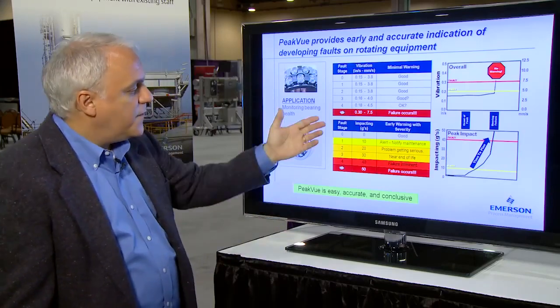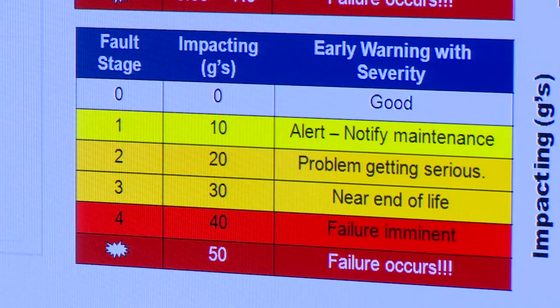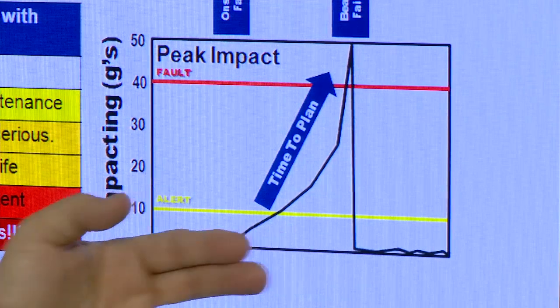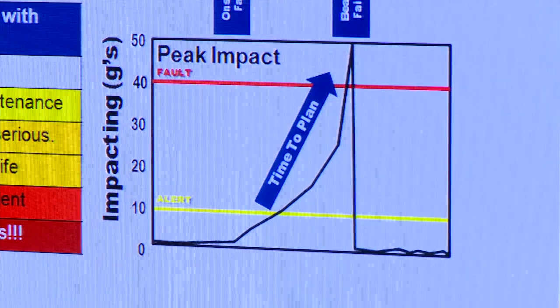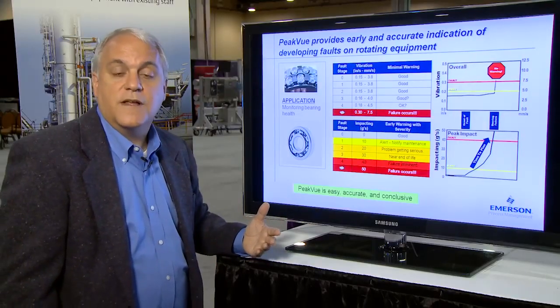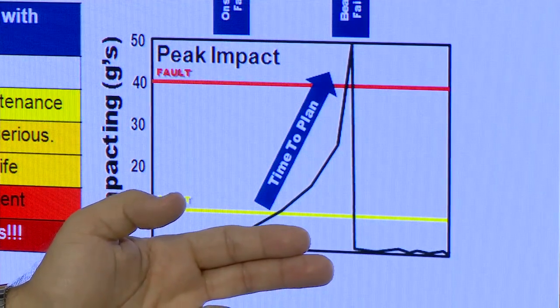In contrast, if we look at PeakVue, the PeakVue amplitudes continue to increase upwards of 50 G's, rising as high in some cases as 80 or 100 G's, prior to the failure of the bearing. Looking at the trend, you can see the continued upward slope of the curve of the PeakVue graph, indicating that the machine is moving towards failure. PeakVue is excellent for diagnosing and tracking rolling element bearing defects, as illustrated in this chart.